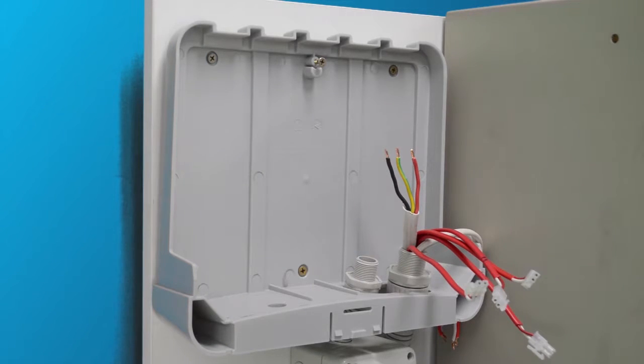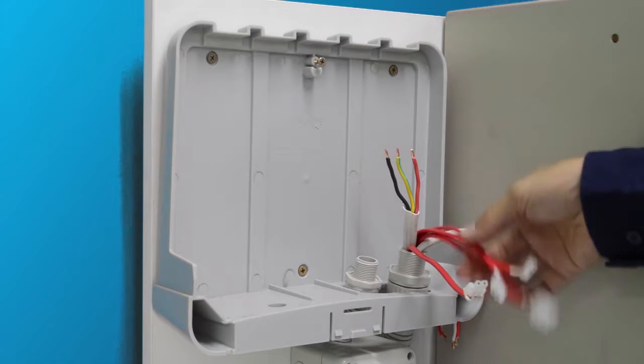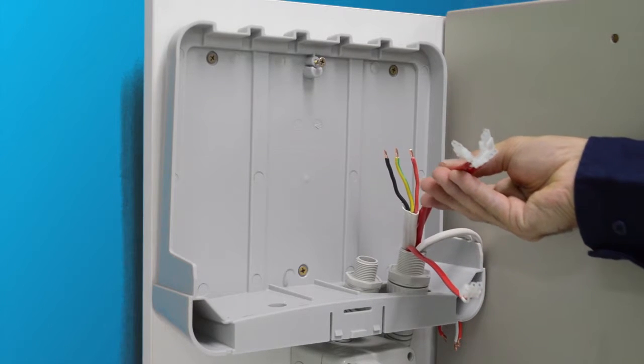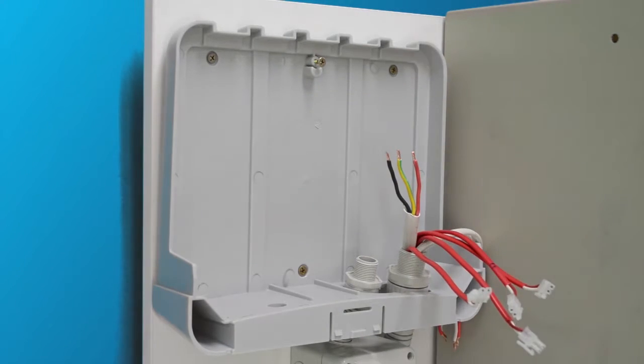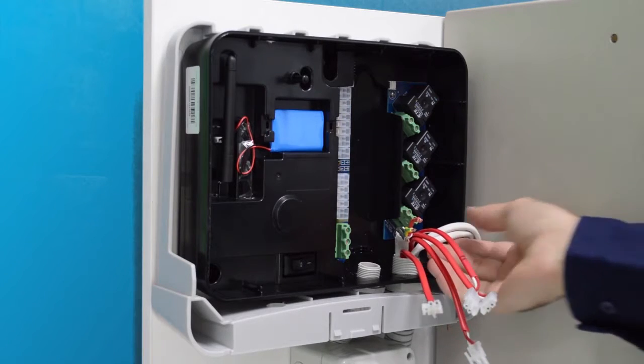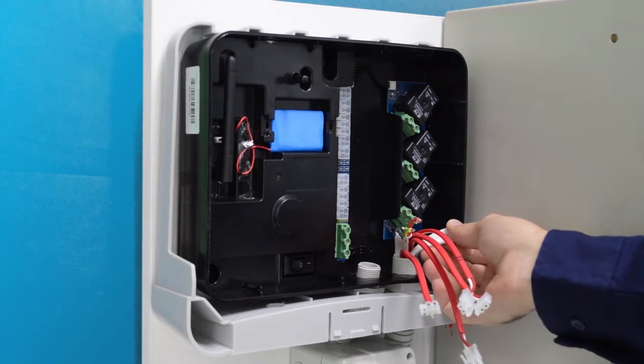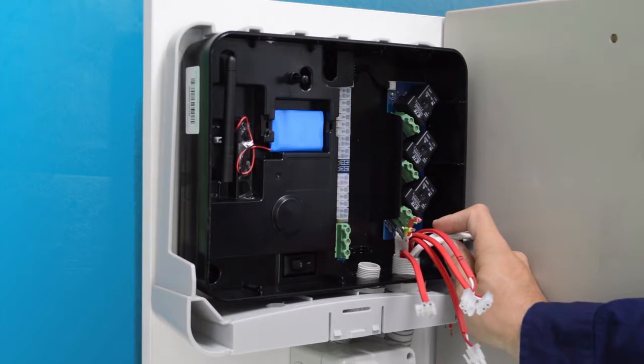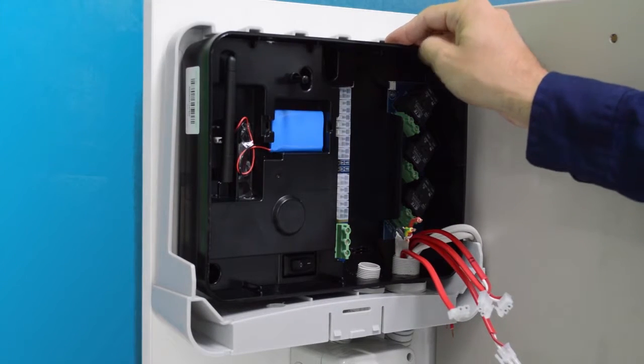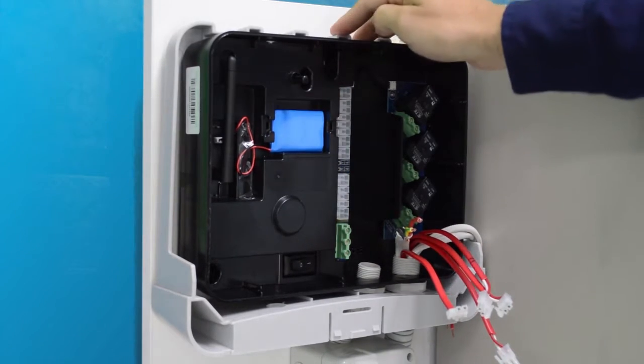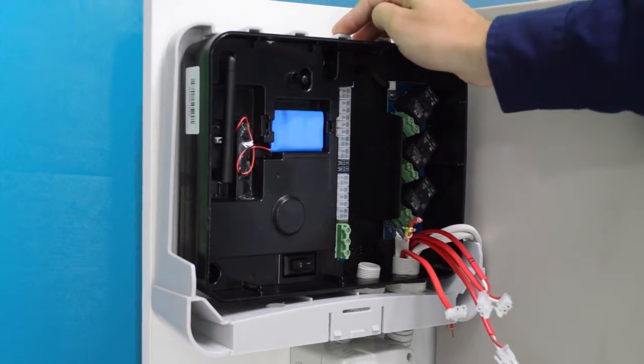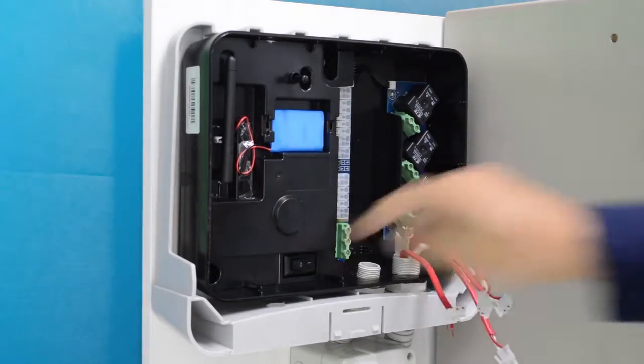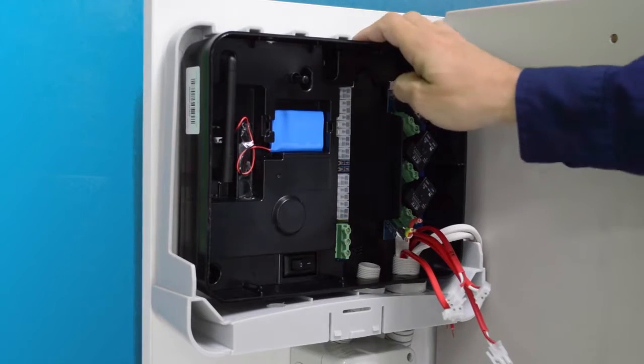Please note the current clamps must be run with the current clamp end in the switchboard and the Molex heads in the unit. As you can see, as this is a test unit, we have some extra cables which we'll be ignoring for this section. Just noting, if it is an internal install and the weatherproof case is not necessary, you would drill and mark the mounting holes for the black unit only.